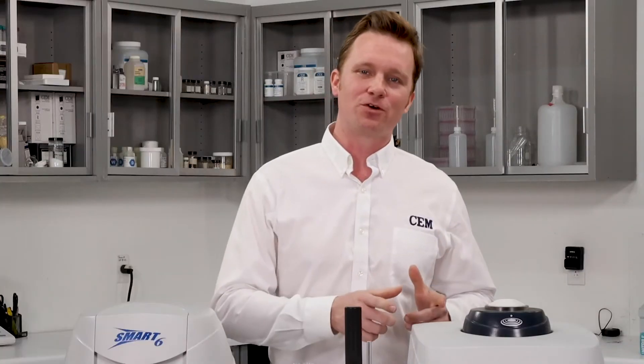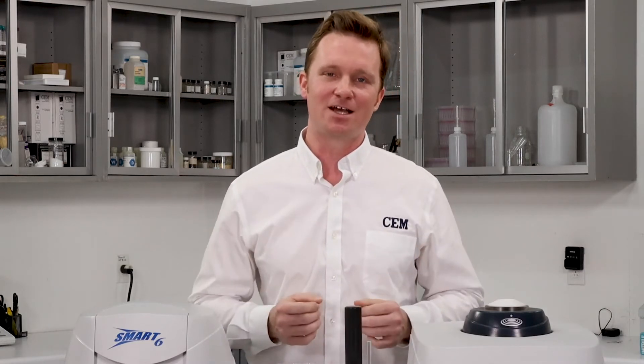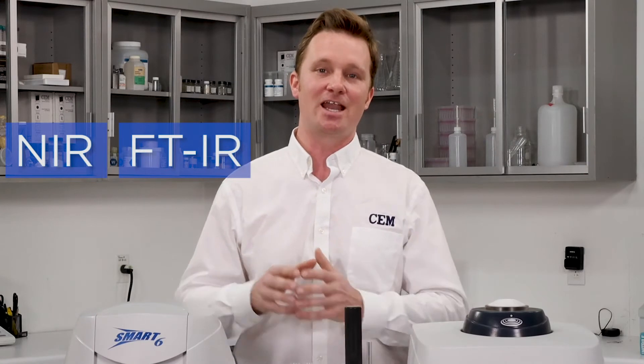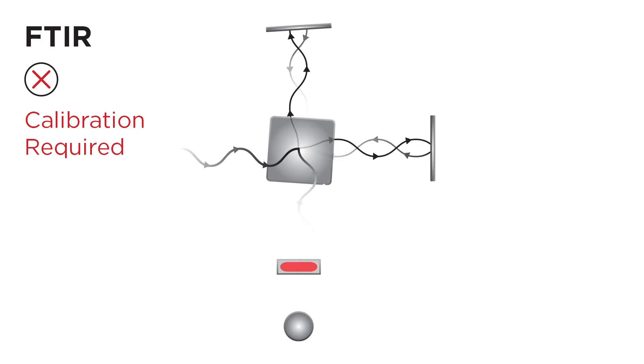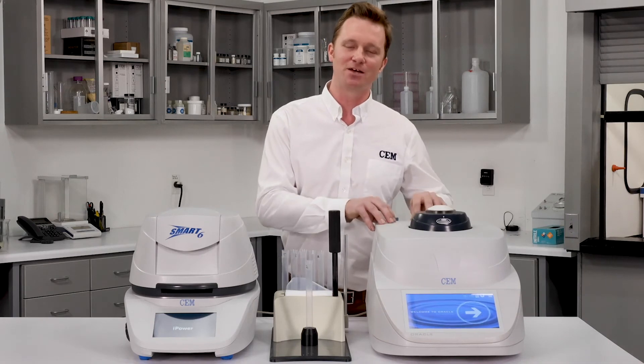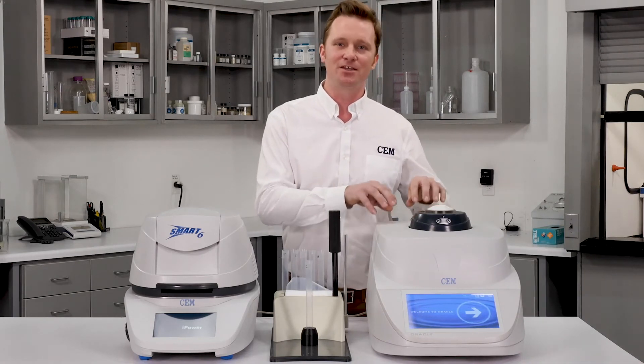Now that we've seen how the Oracle compares to other NMR analyzers, let's take a broader look at how it compares to other rapid fat analyzers on the market — specifically NIR and FTIR. These are both spectroscopic methods that take an optical signal and through chemometrics generate a fat result. The issue is that they have a complex optical train that requires constant recalibration in order to maintain accuracy. The Oracle, by contrast, has no moving parts and maintains reference-level accuracy day in and day out.